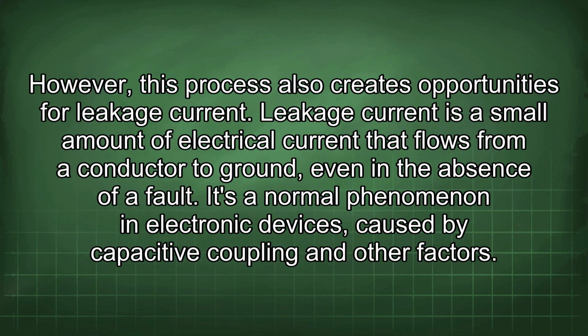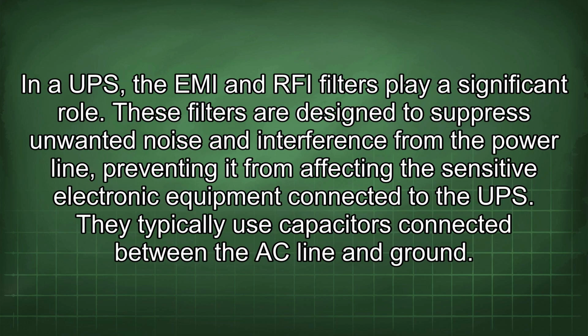However, this process also creates opportunities for leakage current. Leakage current is a small amount of electrical current that flows from a conductor to ground, even in the absence of a fault. It's a normal phenomenon in electronic devices caused by capacitive coupling and other factors. In a UPS, the EMI and RFI filters play a significant role. These filters are designed to suppress unwanted noise and interference from the power line, preventing it from affecting the sensitive electronic equipment connected to the UPS.